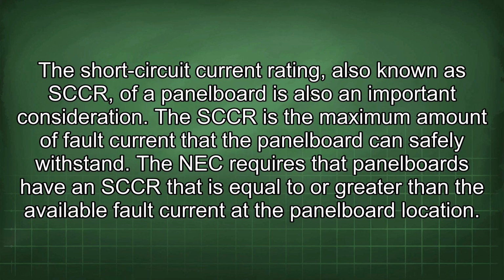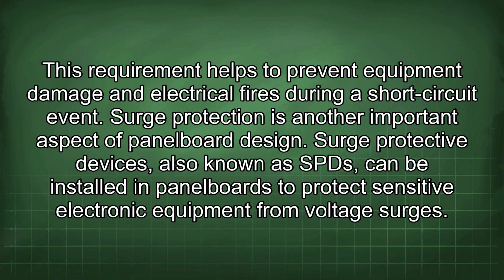The short circuit current rating, also known as SCCR, of a panel board is also an important consideration. The SCCR is the maximum amount of fault current that the panel board can safely withstand. The NEC requires that panel boards have an SCCR that is equal to or greater than the available fault current at the panel board location. This requirement helps to prevent equipment damage and electrical fires during a short circuit event.